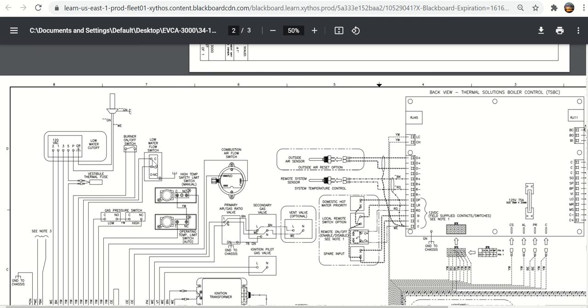Maybe we haven't explained this well enough, or maybe I should explain it another time just to make sure everybody understands. A low water cutoff and a low water flow switch are two completely different things. This one measures the level in the boiler to make sure there is actually water in the boiler. This one measures whether or not there's flow through the piping, and the flow switch is always going to be mounted on the piping, probably leaving the boiler on the outlet pipe. But one will shut the boiler off if the water level is low. This one will shut the boiler or burner off if there's not enough flow going through the boiler.